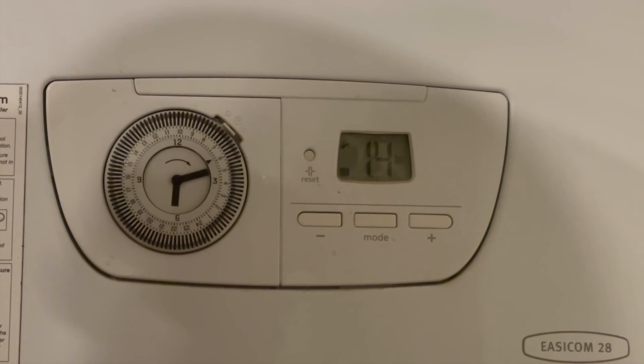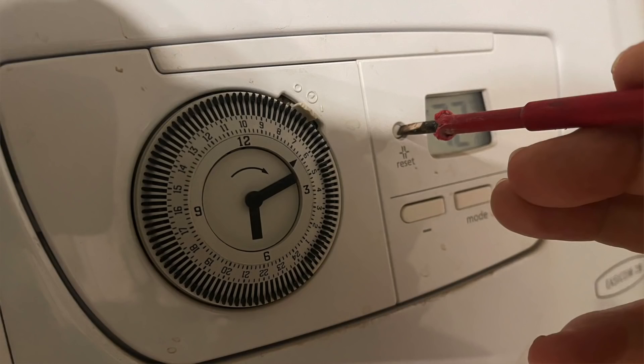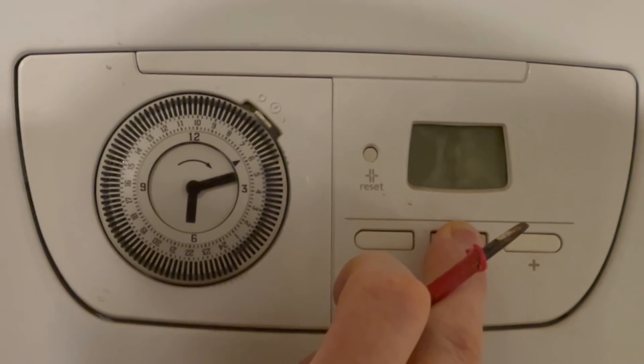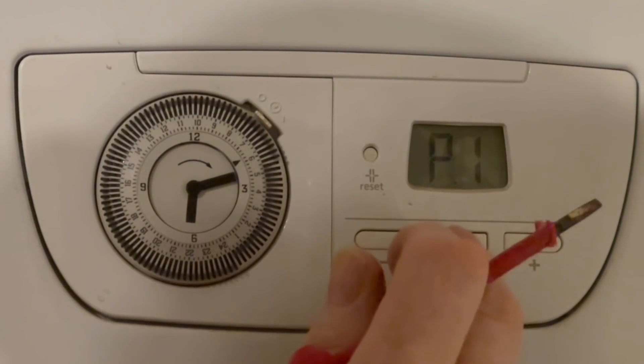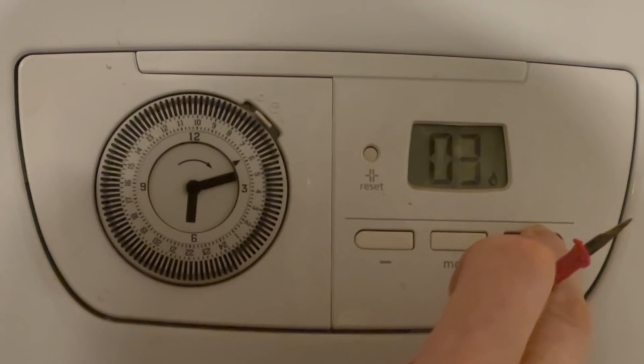Here we have the Glowworm Easicom 28. To put this into service mode, using a screwdriver or a pen press in the reset button, then hold the mode button until the screen goes blank. It will then bring up P1. Accept P1 and that puts us into low mode for analysing — you'll hear the boiler ramp down. Now in low mode, we can use the plus button to take it up to 100 percent.